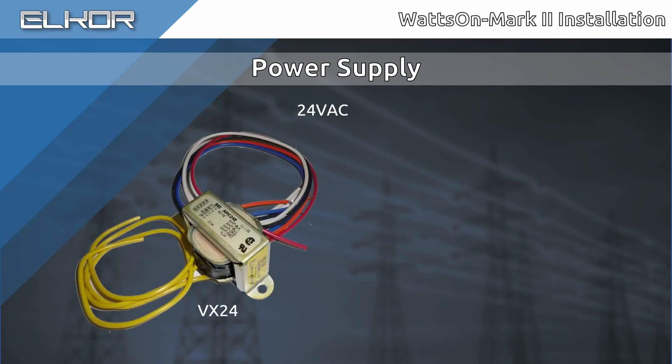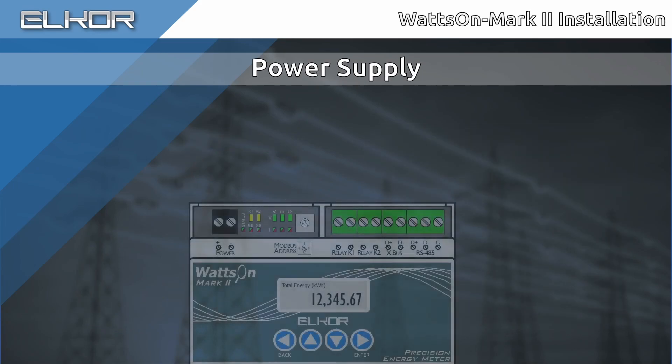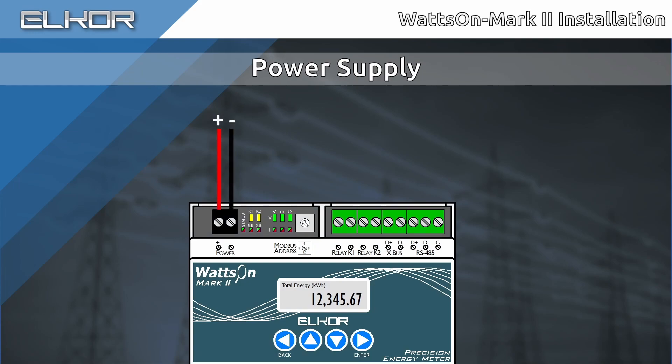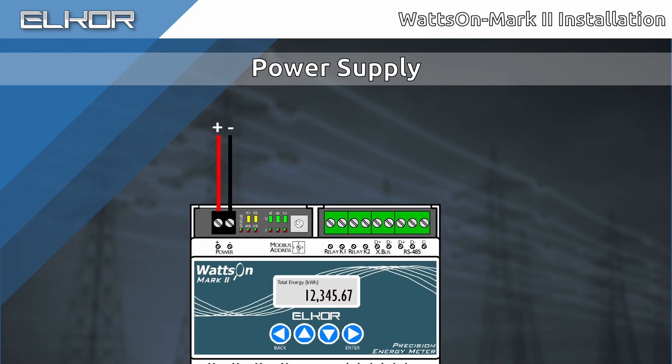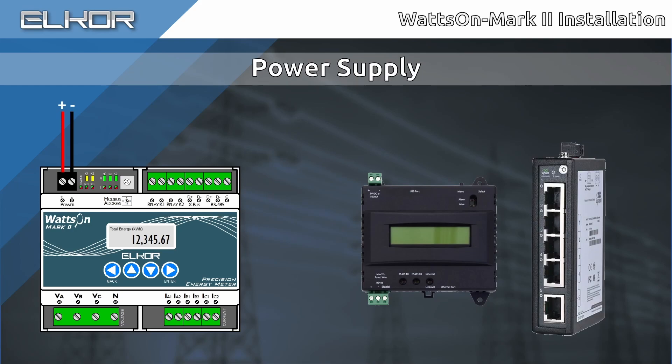Elkor's VX24 may be used for input voltage flexibility, including 277, 347, 480, and 600-volt AC taps. The power supply is wired to the top-left black terminal. Observe the polarity. Note that the output communications G terminal is electrically tied to the power supply negative terminal. The power supply may be shared with multiple pieces of equipment such as data loggers, gateways, or other sensors. If using a DC output power supply and sharing it with other equipment, make sure to note the polarity into each piece of equipment to avoid ground loops, which could damage the power supply or any connected equipment.